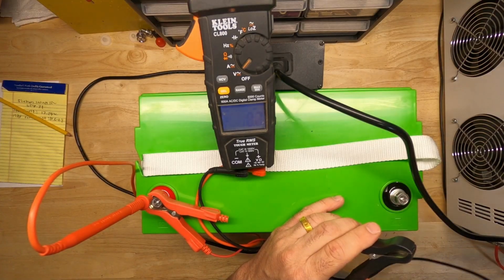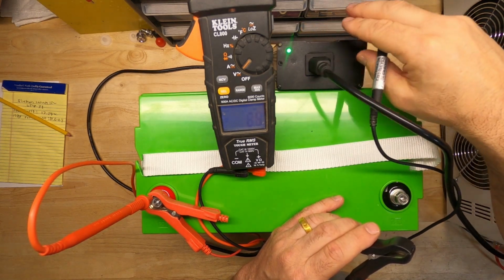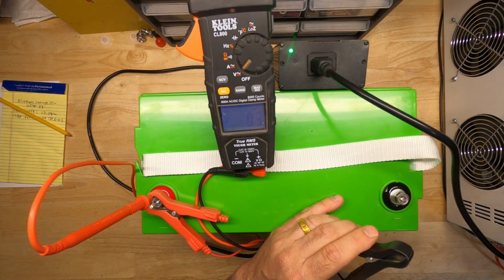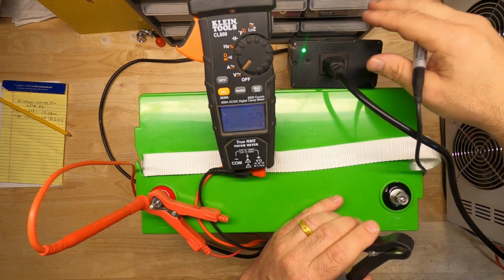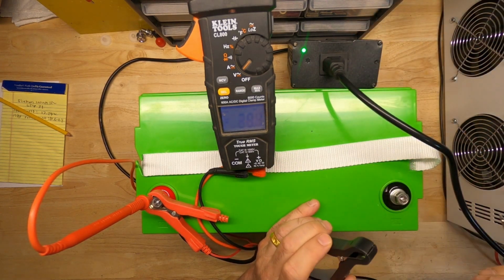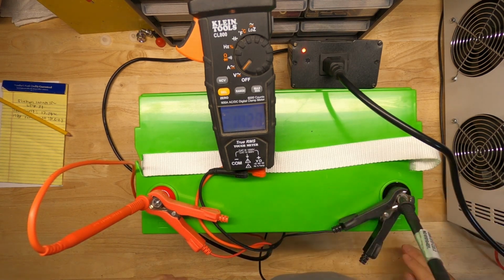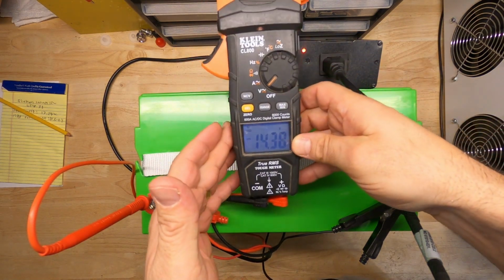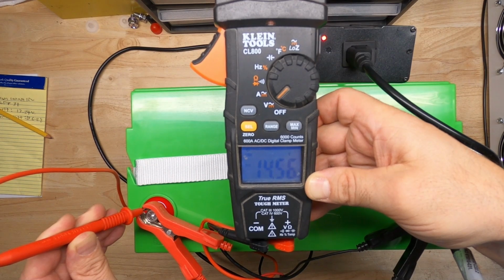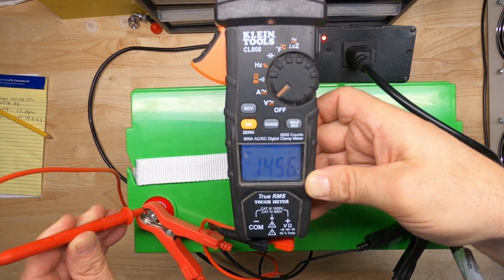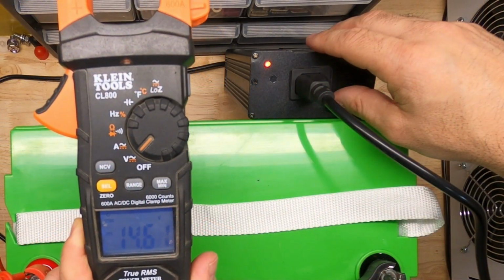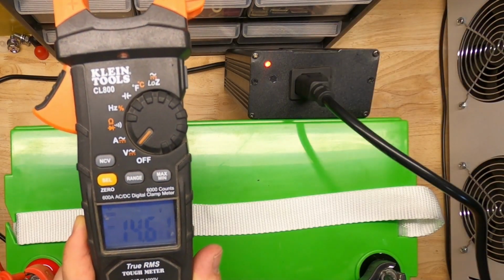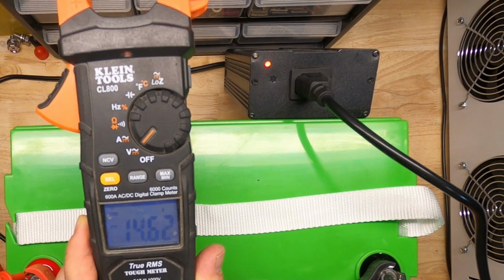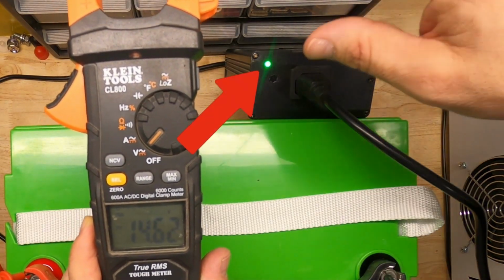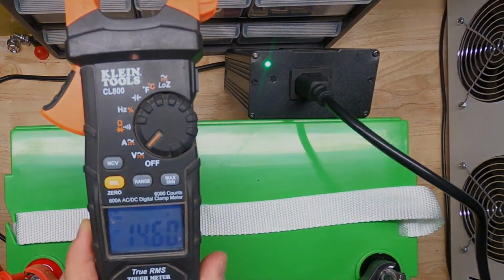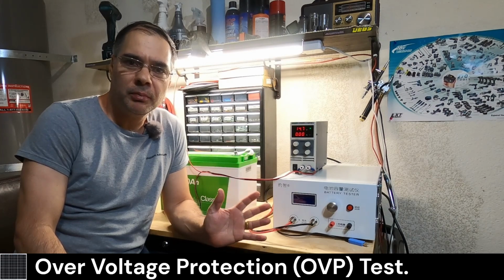So another way to do the resting voltage test is just plug in the charger after you've already charged the battery, and it should top off the charge relatively quick, within about a minute or so. We can also check that the cutoff voltage is 14.6 volts. So we're already at 14.38. About 30 seconds. 14.61. There it is, it cut off. 14.61 on the nose. Okay, so now we're going to test the BMS's over voltage protection feature.